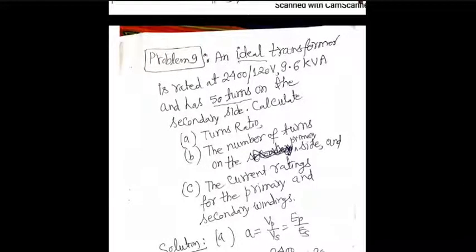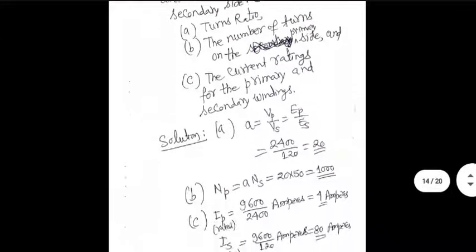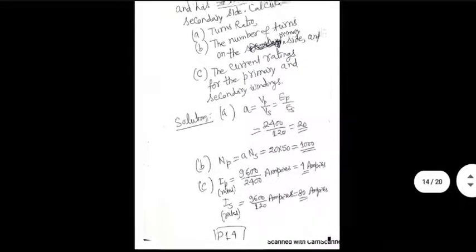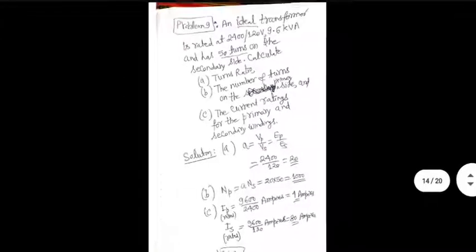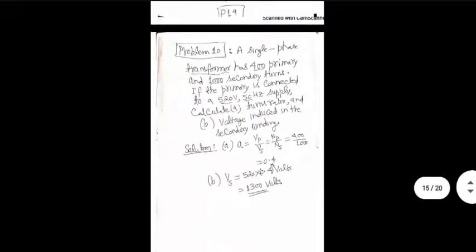Okay, this one is also not too difficult, I think. Straight calculations. kVA divided by primary voltage will give you maximum or full load primary current, magnitude at least. kVA divided by secondary voltage will give you full load secondary current. That is one thing you should always keep in mind when doing these elementary calculations that even mechanical engineers can do very well.